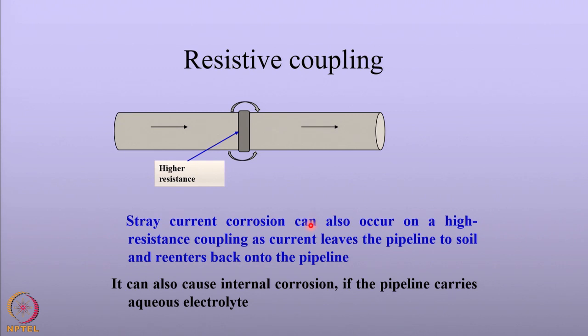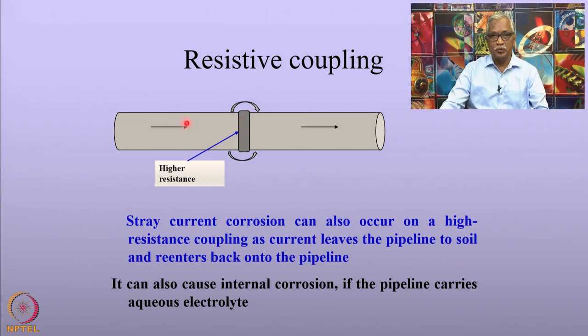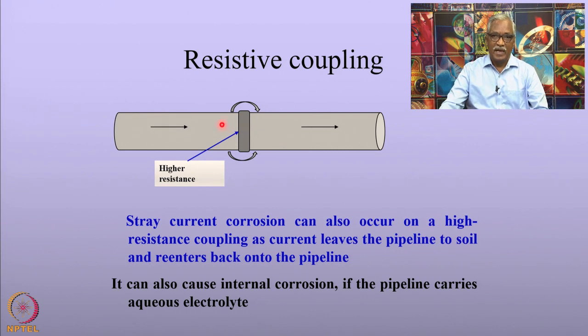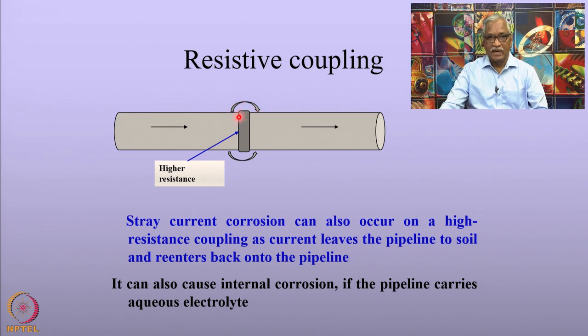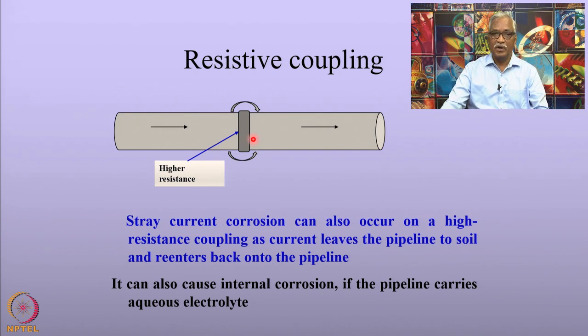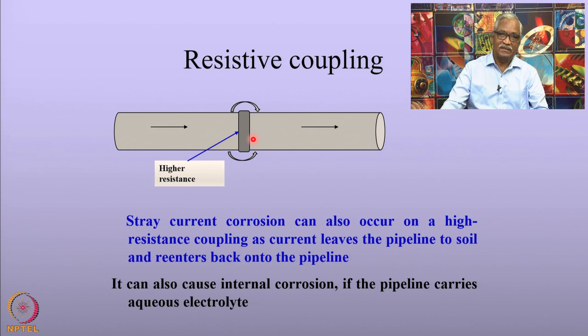There is another kind of stray current corrosion different from what we have seen so far. Assume there is a coupling joining two segments of a pipeline that offers higher resistance. As a consequence, a current leaves this pipeline into the soil and reenters the pipeline at the other end. Where the current leaves, the pipeline suffers corrosion. It is also important to notice that when you have such a resistive coupling, internal corrosion can also occur because the current can jump within the pipeline.